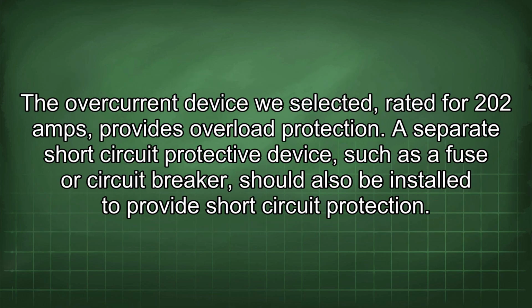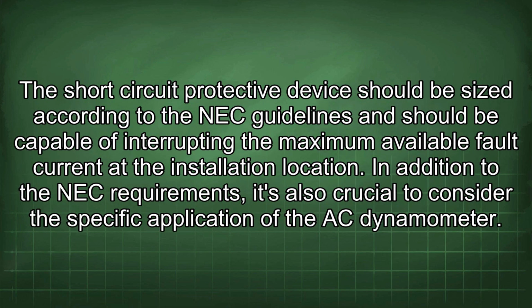The overcurrent device we selected, rated for 202 amps, provides overload protection. A separate short-circuit protective device, such as a fuse or circuit breaker, should also be installed to provide short-circuit protection. The short-circuit protective device should be sized according to the NEC guidelines and should be capable of interrupting the maximum available fault current at the installation location.